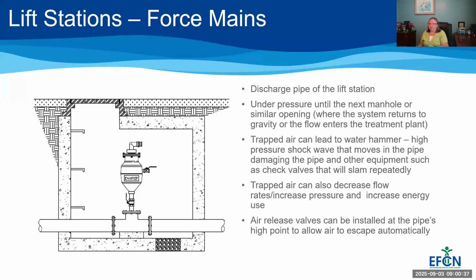So our lift station force main, this is our last concept of a lift station. This is the discharge pipe of the lift station. So the water comes out of the pump and it goes into the force main. As I mentioned earlier, it is under pressure until the next manhole or a similar opening. So it could be your treatment plant headworks, it could be some other type of opening, but this is where the system would return to gravity or the flow enters the treatment plant.